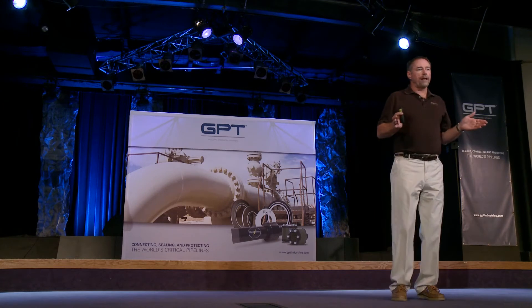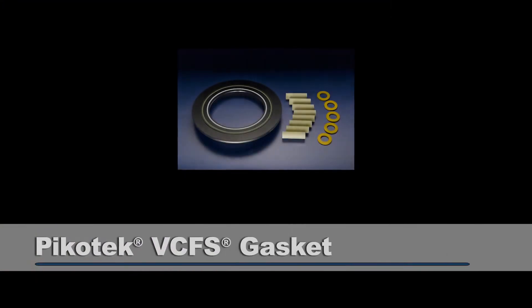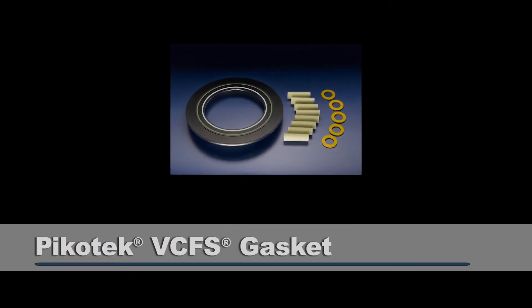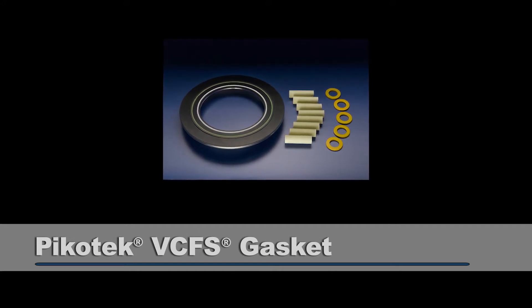It kind of goes without saying, but so many times I've seen it — flammable materials going through the pipeline need a fire-safe product. Quite frankly, about 98% of the sales at GPT are for non-fire-safe gaskets or kits, and I know that they're going into flammable applications. So if there's going to be an asset integrity program, it really needs to dictate that flammable materials have a fire-safe product.